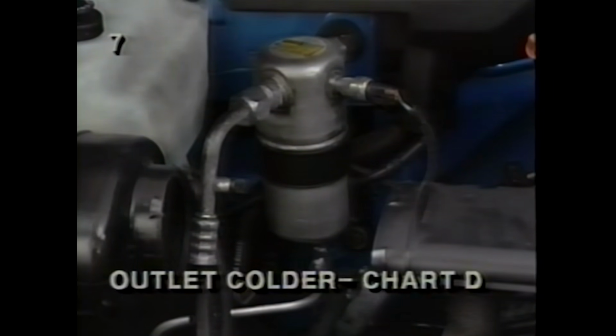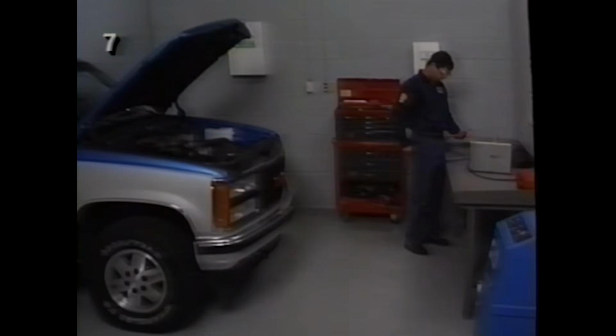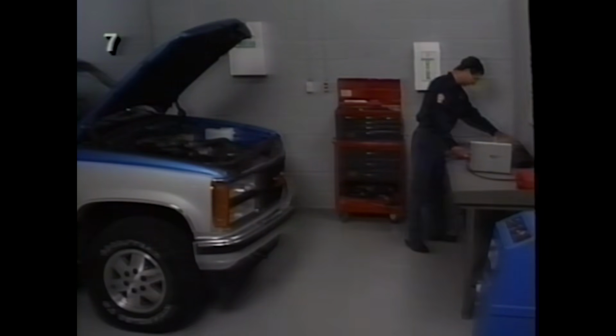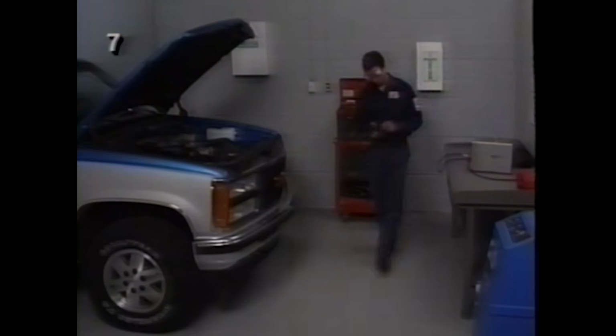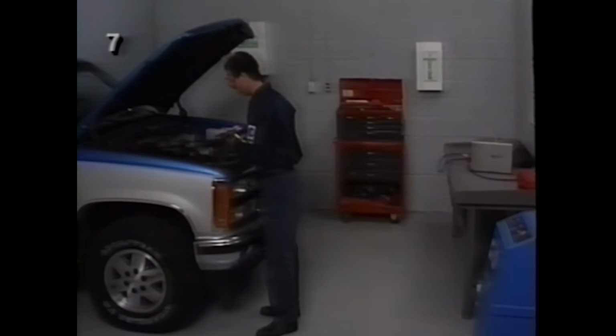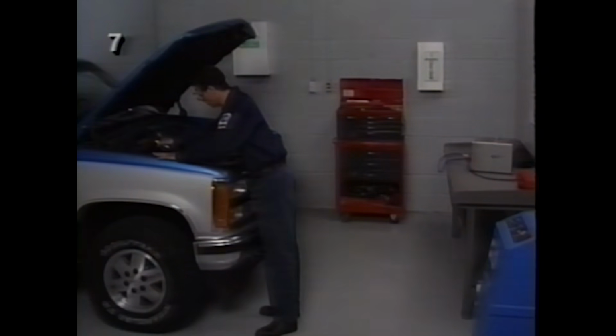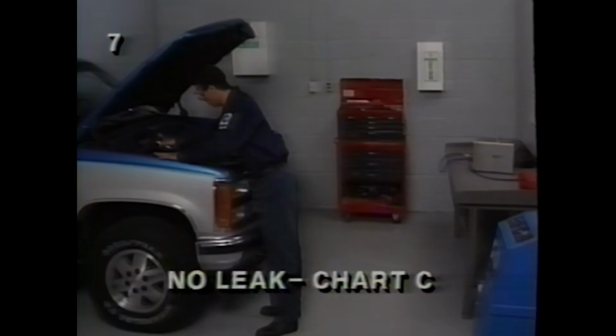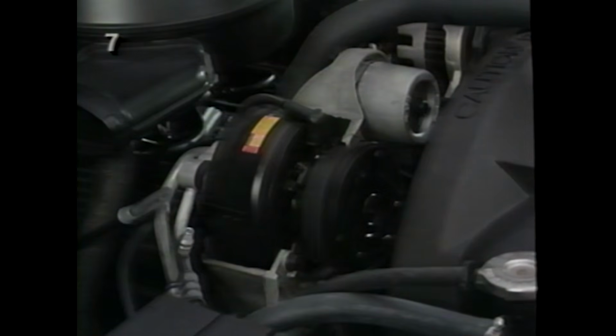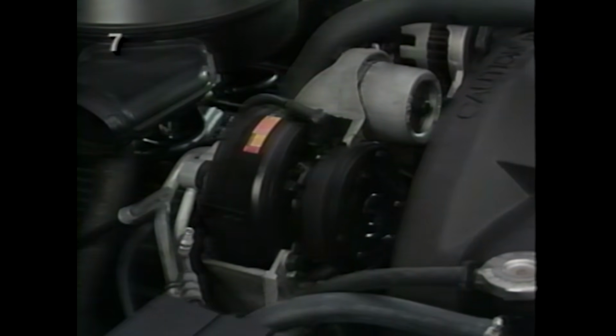If both lines are about the same temperature, or if the outlet is colder than the inlet, go to Chart D in the manuals. If the evaporator inlet is colder than the outlet, leak check the system, especially in or around the evaporator. Recover and repair any leaks found. Then evacuate and recharge the system. Then reevaluate how the whole system works. If you know for sure there are no leaks, go to Chart C in the manuals. In this case, diagnosis charts don't pick up exactly where the last one left off.